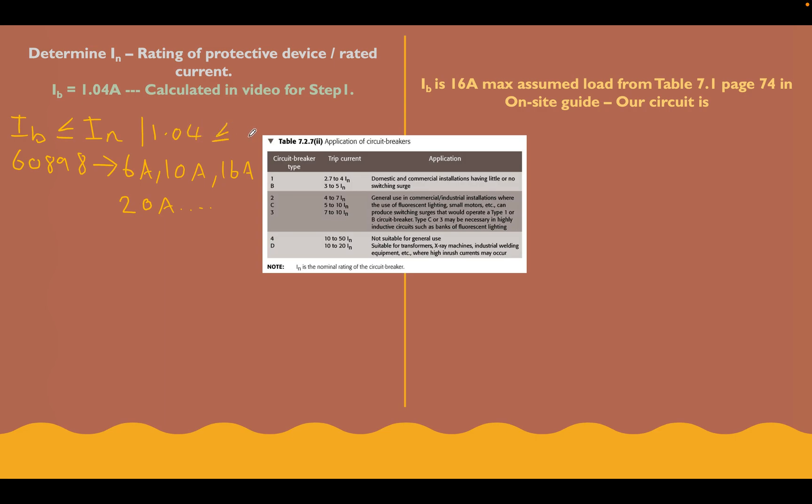Our protective device has got to be greater or equal to that number. Let's have a look. What are our options? 6 amp looks like it's going to be the one. That's the next size up from our design current and it's larger than this number. So let's write this in - 6 amps. What we can say down here is that our IN for this circuit is going to be a 6 amp circuit breaker, and let's come back to this in a minute when we choose the type.